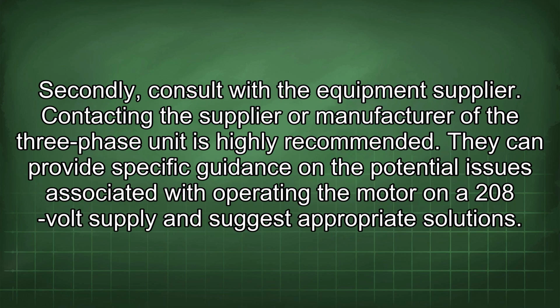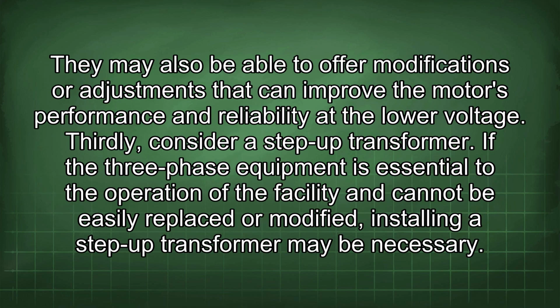Secondly, consult with the equipment supplier. Contacting the supplier or manufacturer of the three-phase unit is highly recommended. They can provide specific guidance on the potential issues associated with operating the motor on a 208 volt supply and suggest appropriate solutions. They may also be able to offer modifications or adjustments that can improve the motor's performance and reliability at the low voltage.